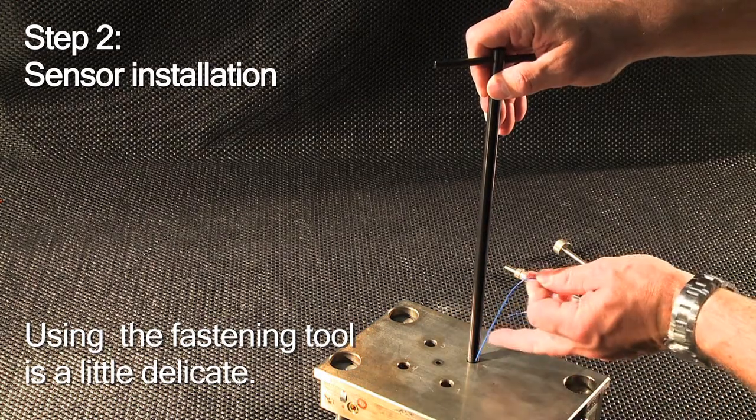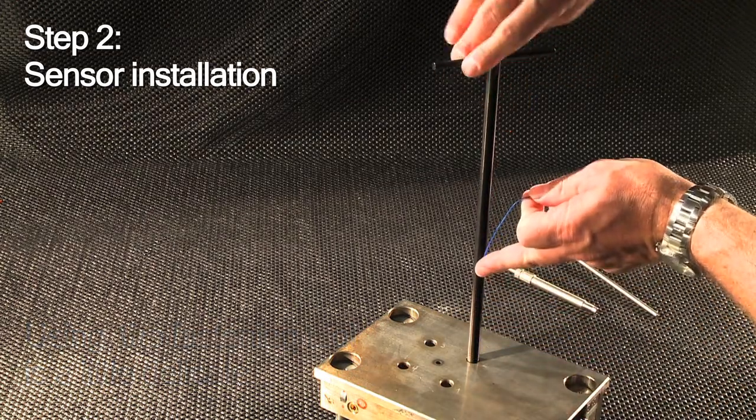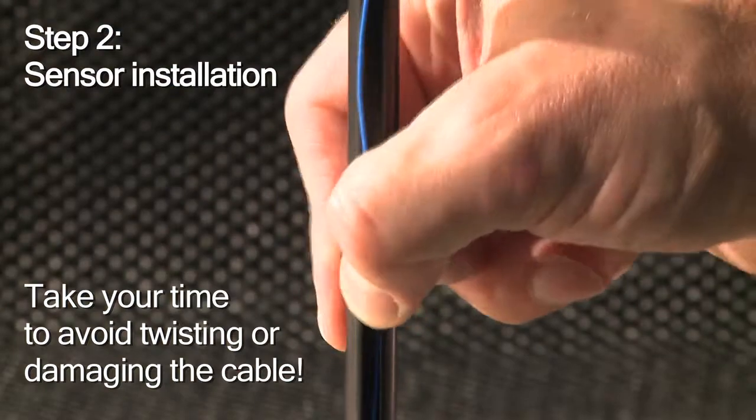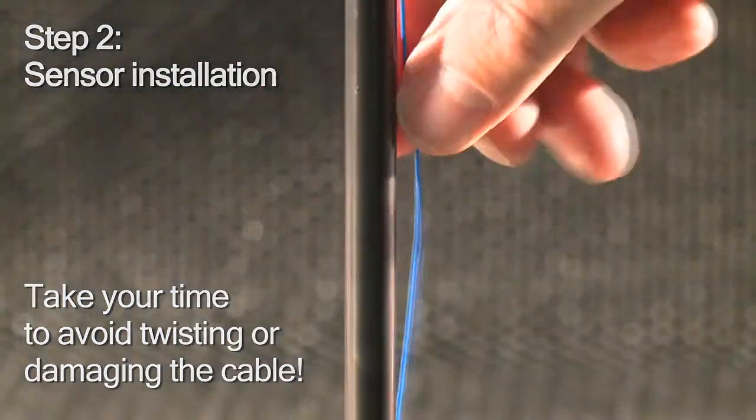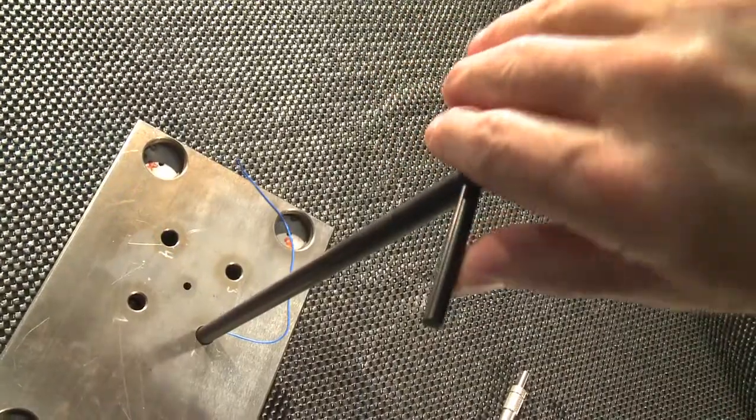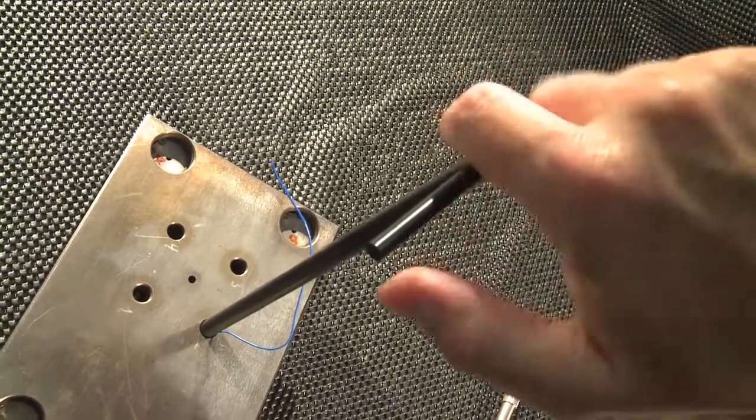Using the mounting nut fastening tool is a bit tricky. As you can see, it has a slit for the cable. It's very important that you take your time. Be careful not to damage the cable. Finally, you tighten manually until the sensor is seated firmly.